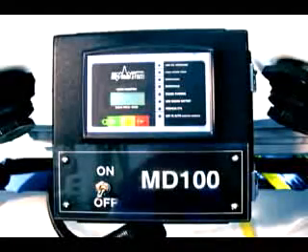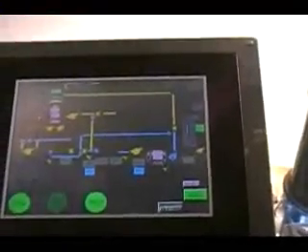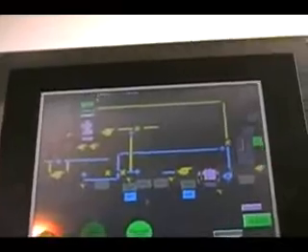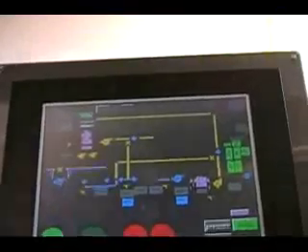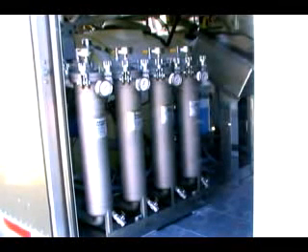The generator is started with a switch and a push button. The operator enters a password on the waterproof NEMA 4 touchscreen and presses the start button. A short automatic sequence begins that warms up the ozone and ultraviolet modules. Contaminated source water is pumped through the intake strainer and then passes through the zeolite filters. Next, the water passes through pharmaceutical-grade bag filters. The housing size and filter porosity is selected for each application. In the case of non-turbid well water, 1 micron absolute filters should be considered. They will block all microorganisms larger than a virus.